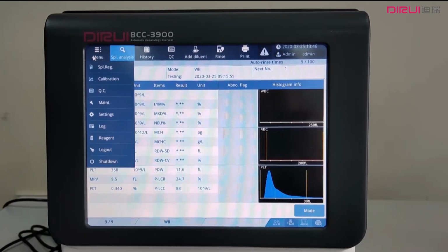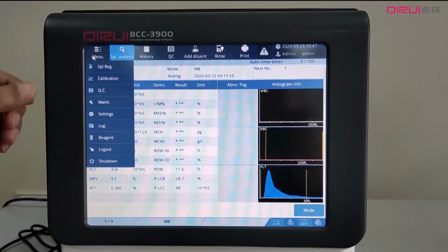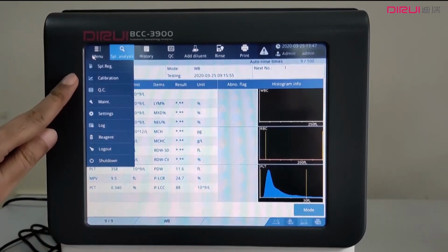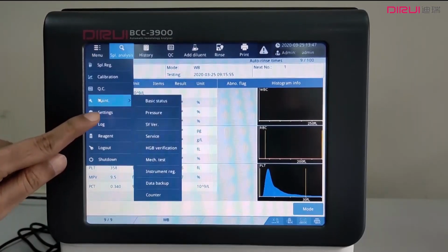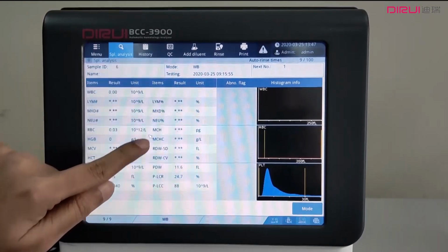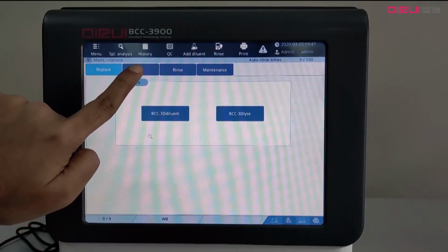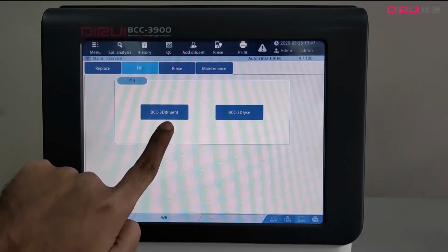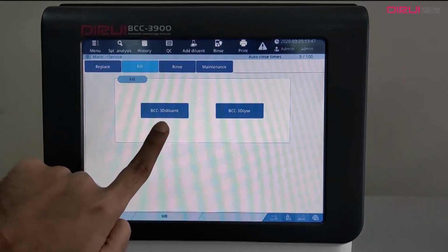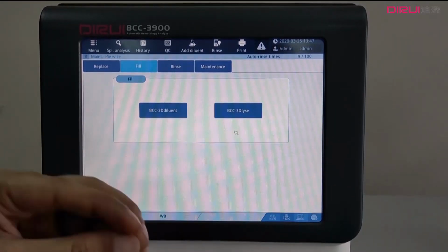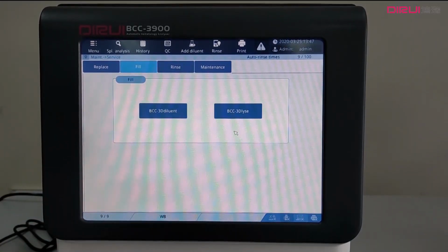After the successful registration of our reagents into the machine, this is the time we want to fill the pipeline. For that purpose, you need to go to maintenance, and then there is a service button. Here you need to press the fill tab, and there are two kinds, diluent and lyse. You need to press them one by one to fill all of the pipeline with these reagents, because currently your pipeline is empty. Before you start testing, you need to fill your pipeline.